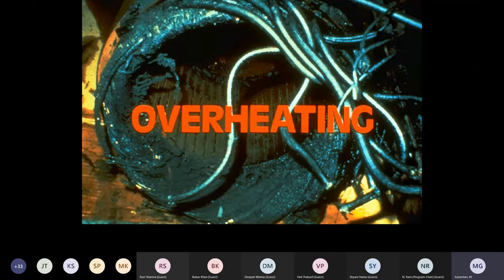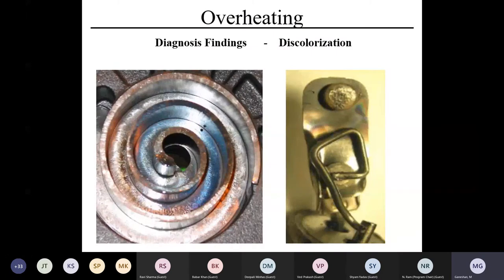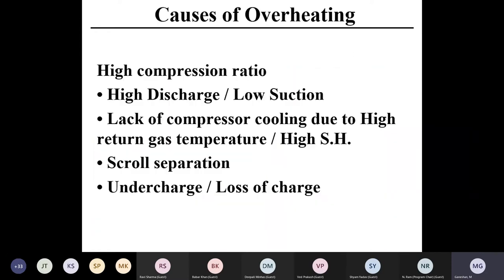Normally the compressor goes from 35 to 130, but when suction is low, say 25, and discharge goes over 150 instead of 130, it is working under overload condition. Naturally there will be high discharge temperature, and our compressors are cooled by refrigerant return gas, so when the return gas is also heating up, heat builds up completely. This is what we call the compression ratio. Whenever you open up a compressor and see highly polished surfaces or heavy discoloration, we can know it's because of overheating. The only reason is high compression ratio: high discharge and low suction, that's all.